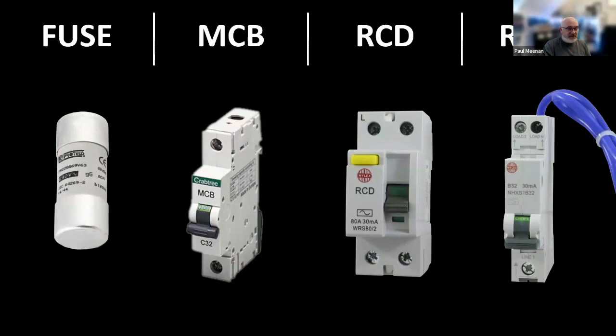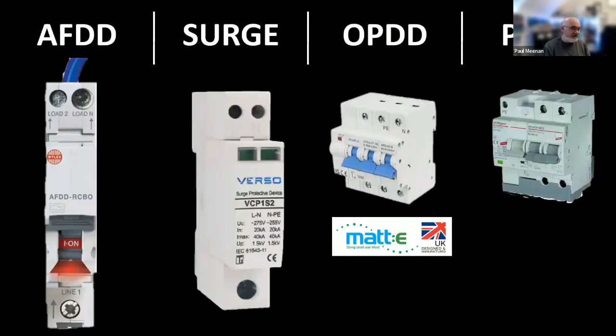We've obviously been on a journey. BS 4293 standard RCDs, which we would use, putting two of them in a board and splitting the installation in half, would look for earth leakage up to 30 milliamps. Thankfully, we have technology, and the wonders of technology allowed compact RCBOs, which you then have a little neutral reference lead for. And that's standard what we do now in most installations, probably in the last 5 to 10 years in the UK. And that's a Type A as well. Interestingly enough, some of them have additional leads as well, functional earths, because some of them may rely on a connection to earth so that they can operate and function correctly, get an earth reference.